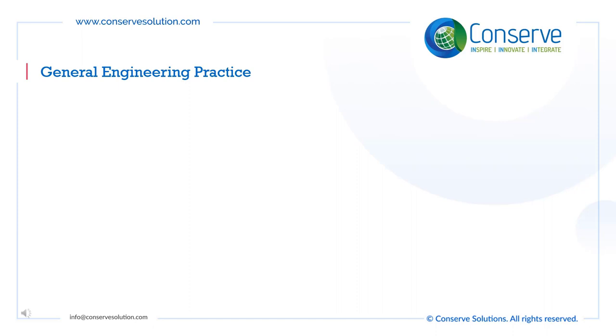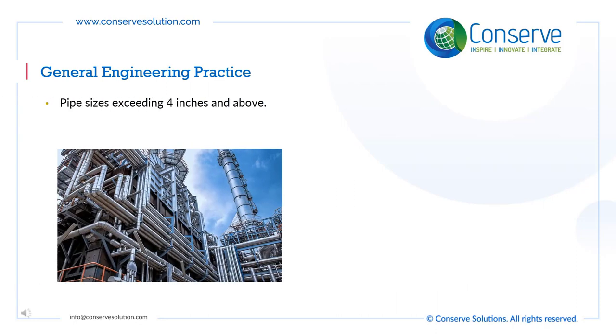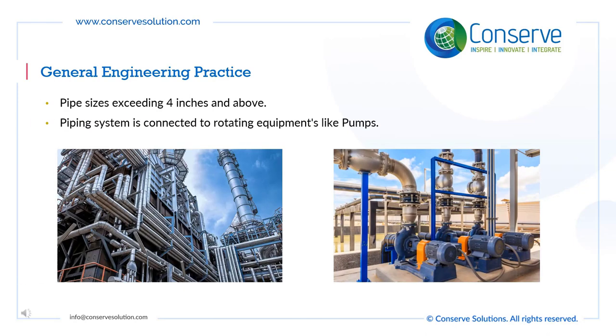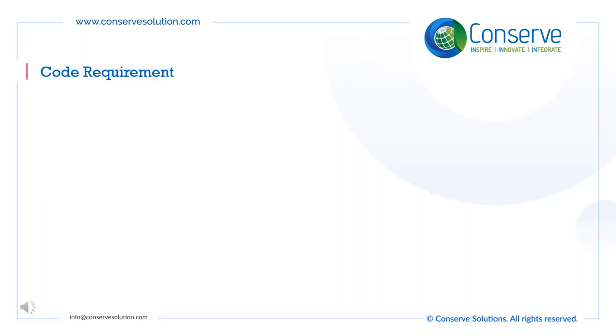As a general engineering practice, stress analysis is required for piping systems with pipe sizes exceeding 4 inches of diameter. So if you have a small network with pipe sizes less than 4 inches, stress analysis may be excluded. However, if the piping system is connected to rotating equipment like a pump, it is essential to perform stress analysis. If you have to comply with piping codes, then stress analysis may be required.